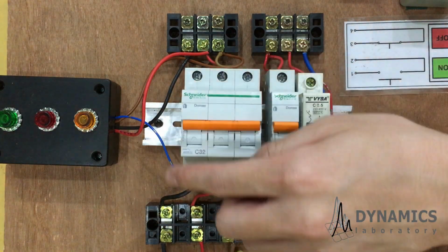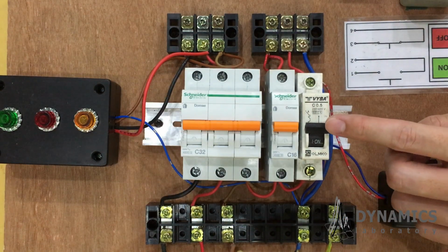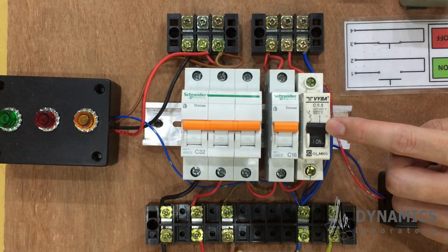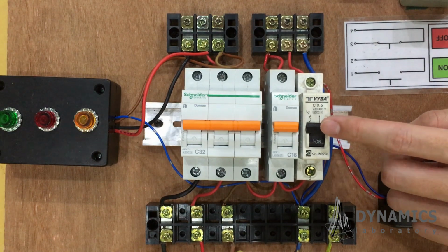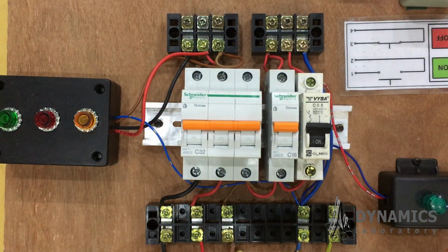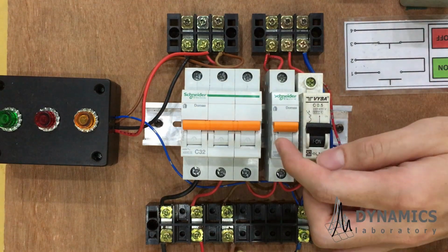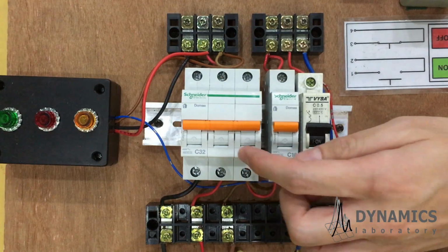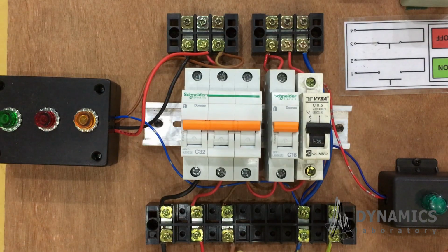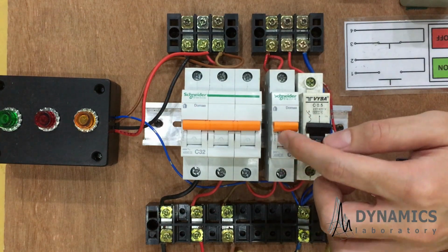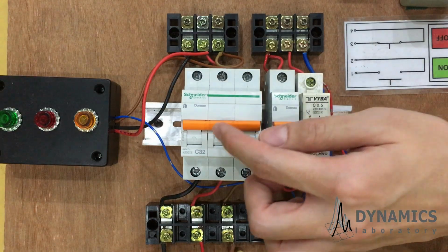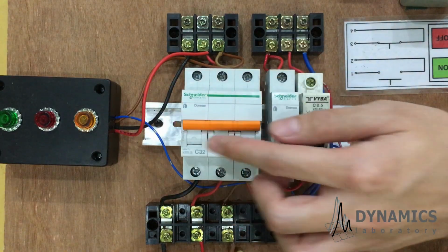From all circuit breakers, this circuit breaker with black lever is called the control circuit breaker, because it has the smallest current capacity. Therefore, we will utilize this circuit breaker for the control circuit. Later, we will learn how to create push button, switch, and also latching control circuit. Meanwhile, these 2 circuit breakers are called load circuit breakers, because we will connect this circuit breaker with one-phase AC motor. Meanwhile, this circuit breaker with 3-phase AC motor.